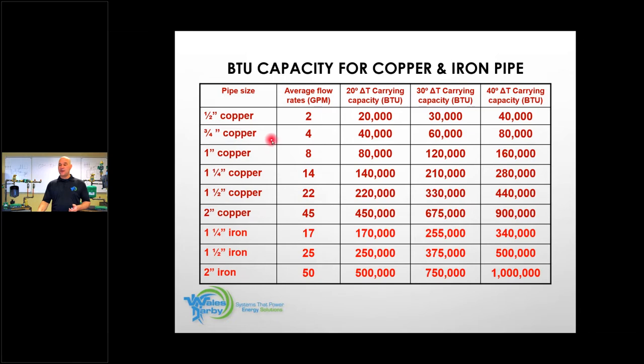3/4 is probably the most common size we use for heat circuits. Good for about 4 gallons per minute. Good for about 40,000 BTU, sorry. That's at a 20 degree delta T, and that's an average flow rate. Can we put more water through there? Yes, we can. Can we put a little bit less water through there? Yes, we can. But if you adhere to those numbers, that will keep your velocity in check so you don't have noise and you're still able to move those little micro air bubbles in the system. That'll give you the ability to move them.